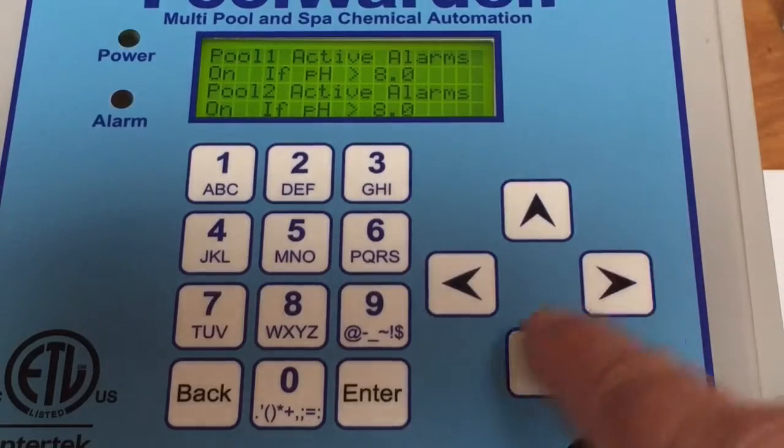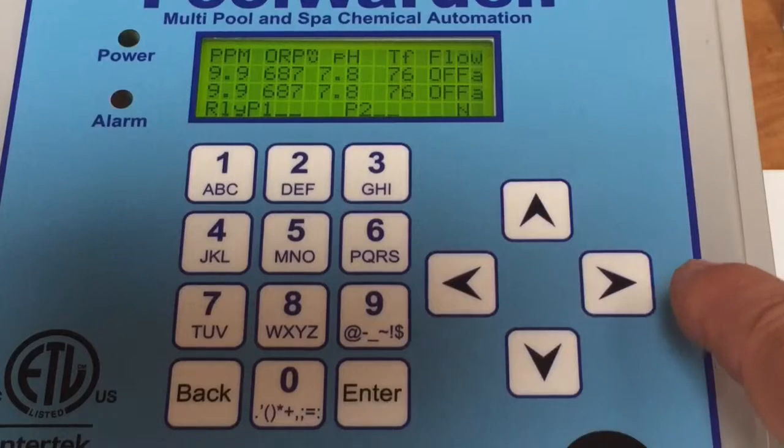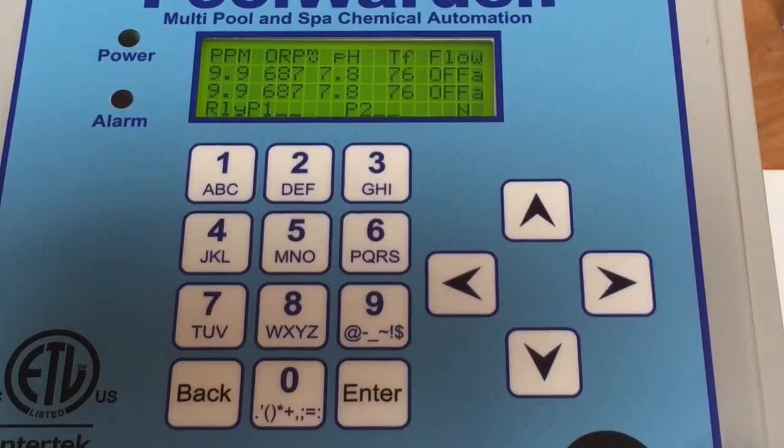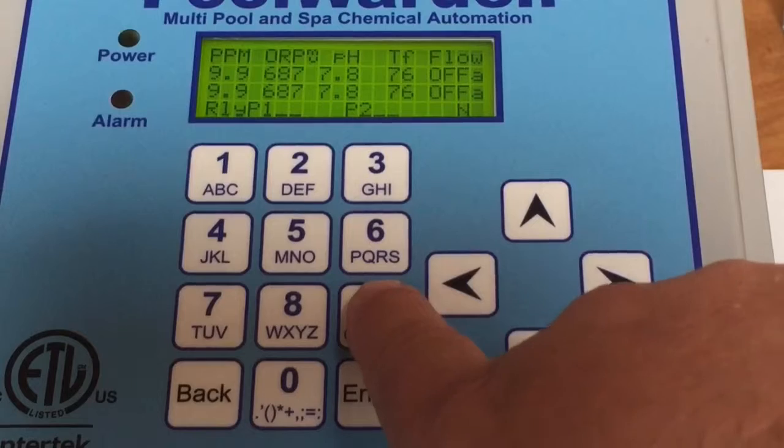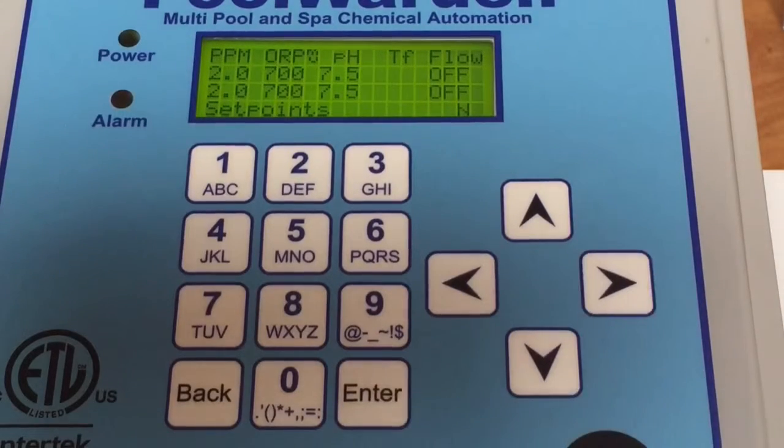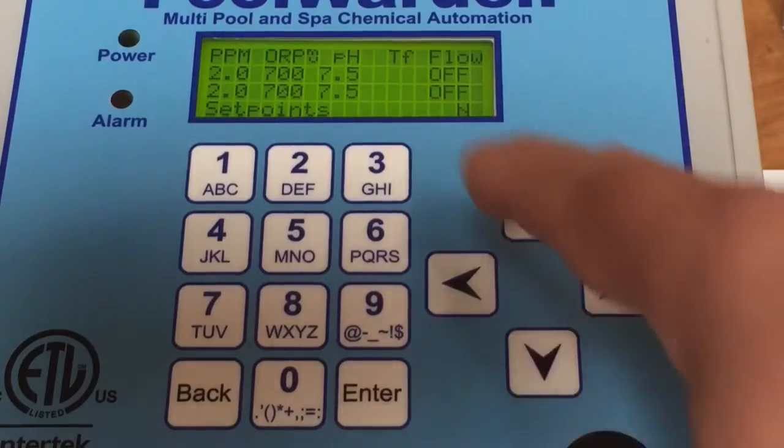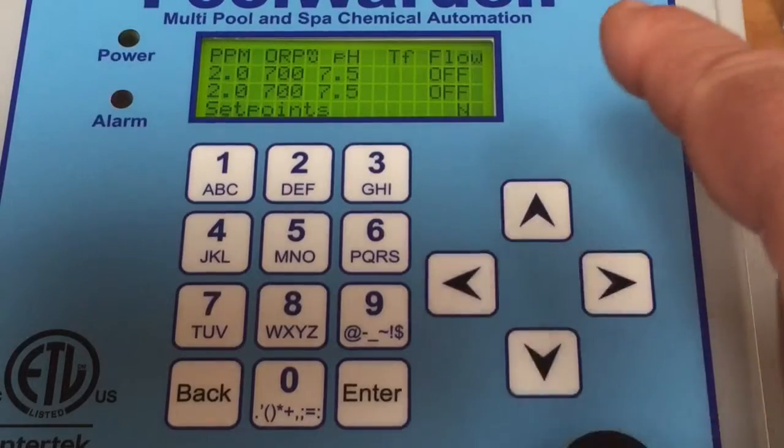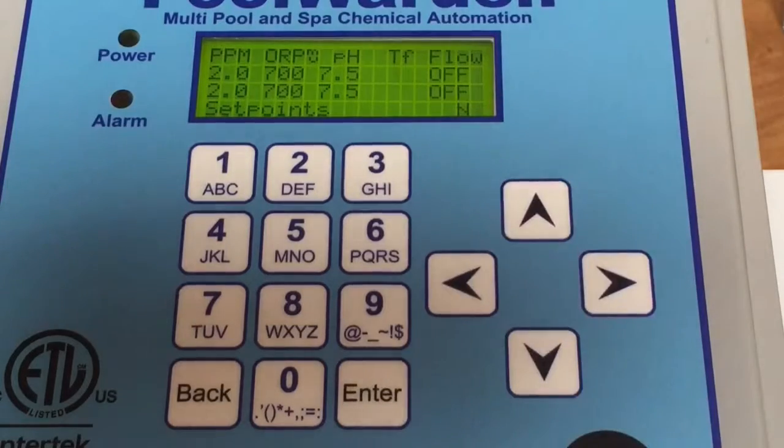Now some of the quick menu features here—if we press the number nine, we'll get our set points. In this case, it'd be 2.0 ppm, ORP 700, pH 7.5. Now remember, if you do not have the True DPD sensor installed on this controller, you will not get the ppm readings.